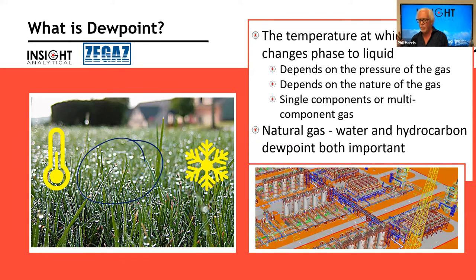In the natural gas processing industry, both the water dew point and the hydrocarbon dew point are important. There are a lot of techniques that we can use to measure water vapor concentration and calculate a dew point from there. But if we want to get to the actual dew point, the Bureau of Mines method, the standard method for assessing dew point, is to cool an object down and see when things condense. And so in natural gas, we'd like to be able to do that both for water and for hydrocarbon dew points.